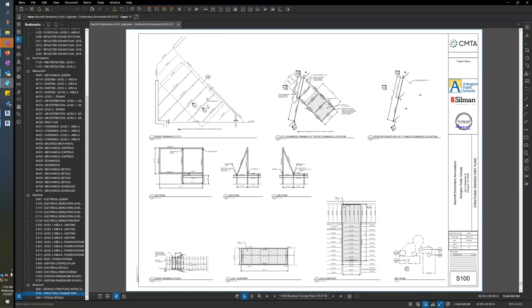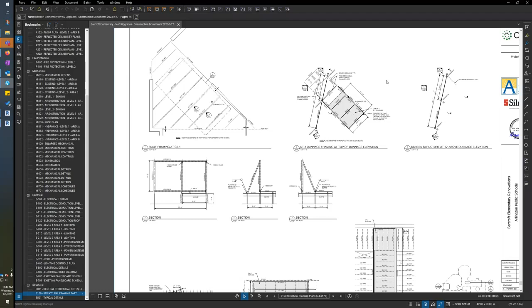Outside of that, there is some existing steel dunnage above the roof, above the main mechanical room, where the current chiller rests. When that chiller gets removed, we're putting the new cooling tower on that existing dunnage, reusing that steel. So we do not expect any major additions to that steel or structure, but we will be adding some screening to help reduce sound and sight visibility to some of the neighbors, as there have been complaints in the past, and we want to help mitigate that as part of this project.